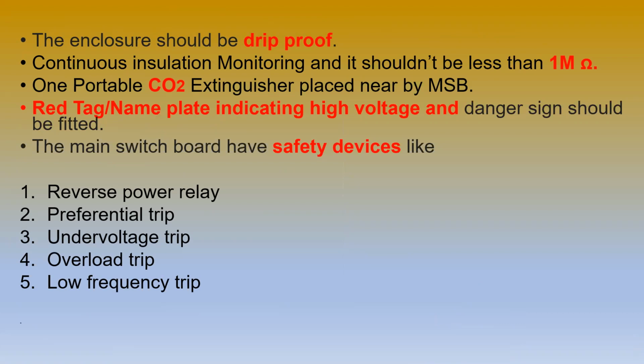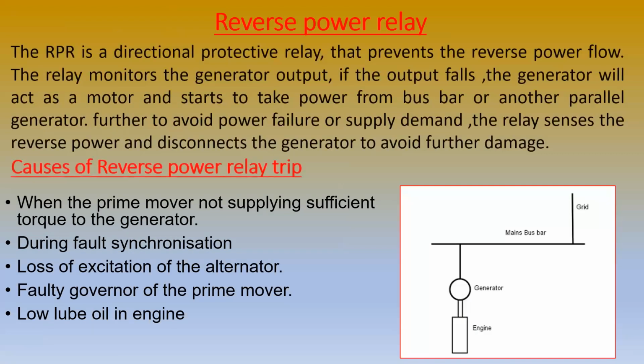Next, what is a reverse power relay? A reverse power relay is a directional protective relay that prevents reverse power flow. The relay monitors the generator output. If the output falls, the generator will act as a motor and start to take power from the bus bar. So to avoid power failure, the relay senses the reverse power and disconnects the generator to avoid any further mechanical damage.